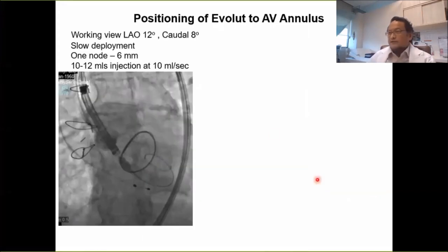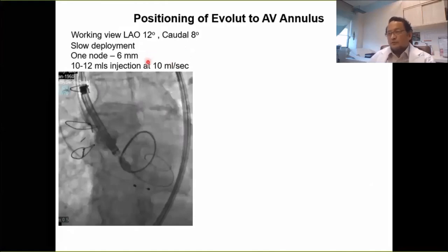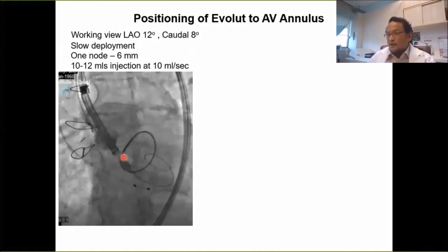So this is valve deployment, slow deployment, and we go by looking at the nodes. This is the tip, the dark marker is where the sheath is, and as we start to pull the sheath, this is the edge of the stent, and you can actually see lines - we call these lines nodes. The first line is 6 mm, the subsequent line is 4 mm.